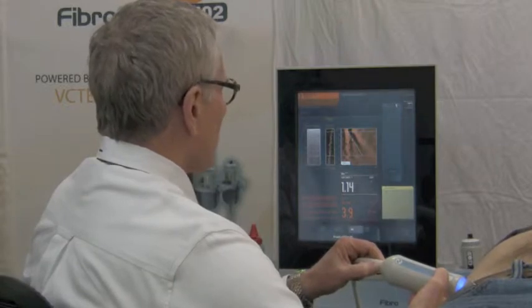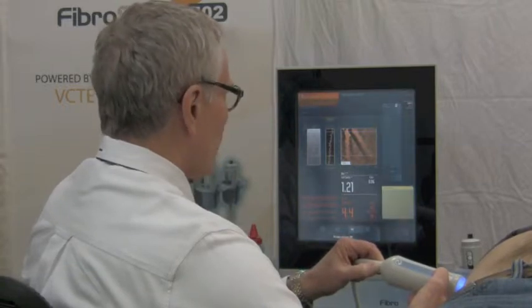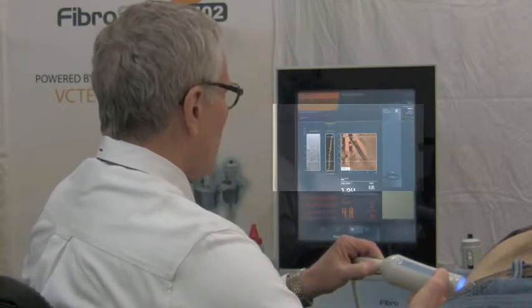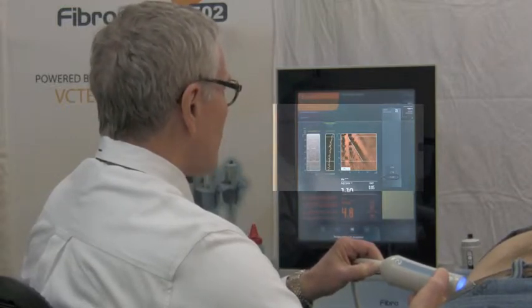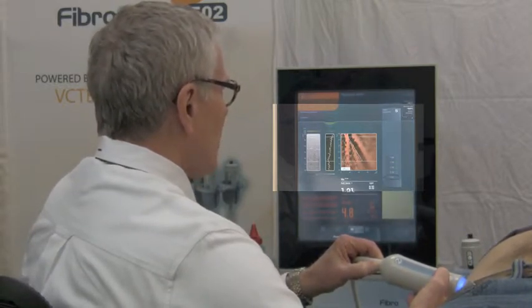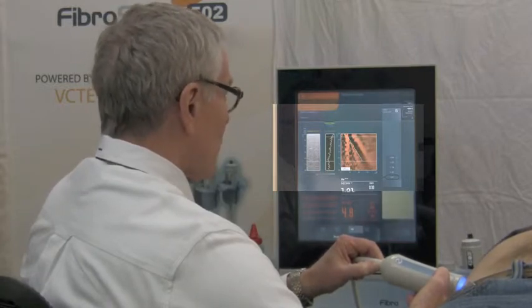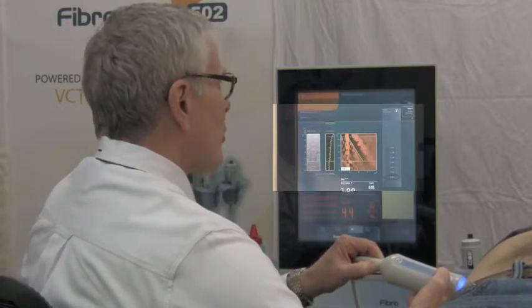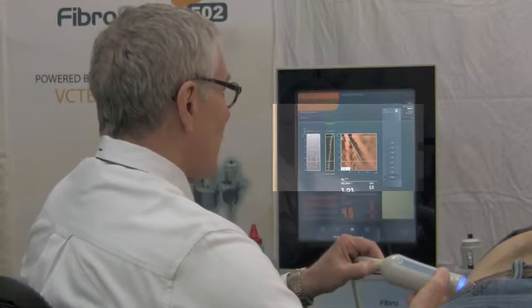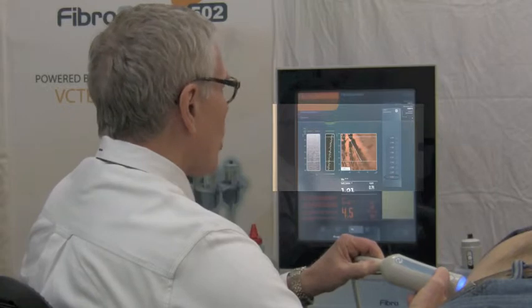You will notice that the left side of the screen remains active. This is my feedback telling me that the probe is in a good location and that I have a good quality signal. You will notice that these measurements are only about 5 seconds apart, and you will also notice that I'm keeping the probe very stationary. We do all of our measurements from the same location. I'm also watching the right-hand side of the screen, which refreshes after each respective measurement, telling me that the measurement was indeed of good quality. We have one more measurement to go, and then the test will be done.